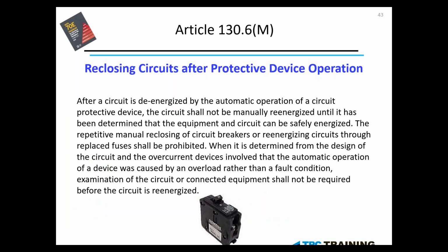Article 130.6M. I like to bring this up in almost every class that I teach. After a circuit is de-energized by the automatic operation of a circuit protective device, also known as a circuit breaker or fuse, the circuit shall not be manually re-energized until it has been determined that the equipment and circuit can be safely energized. The repetitive manual reclosing of a circuit breaker or re-energizing circuits through replaced fuses shall be prohibited. When it is determined that the design of the circuit and the overcurrent protection device involved, that the automatic operation of the device was caused by an overload rather than fault, examination of the circuit or connected equipment shall not be required.